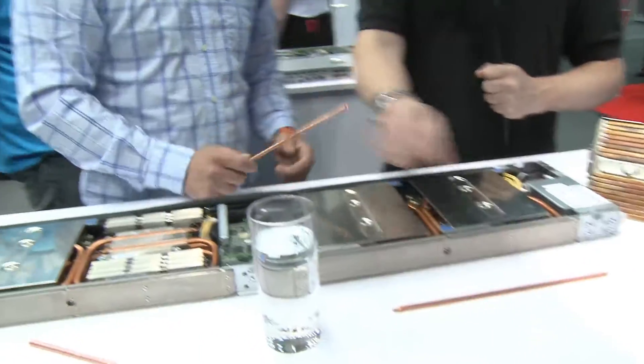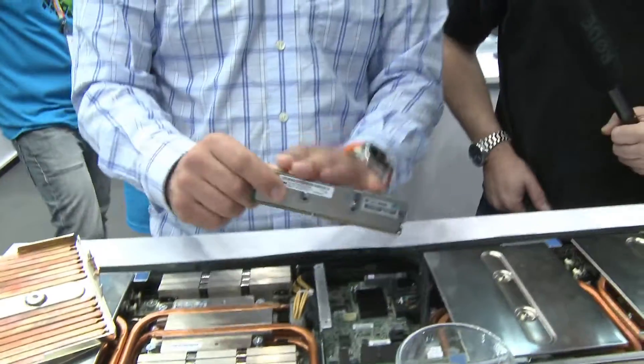That's the technology we're using to get the heat out to these sidebars, and then let the water take that out. We also have a bunch of those heat pipes under that plate here that conduct the heat from the memory. The memory DIMMs have an aluminum jacket on them to help with heat conduction. That travels to the heat pipes, which dump the heat into the top two pipes and goes out. That's basically the whole cooling magic we do in Apollo.